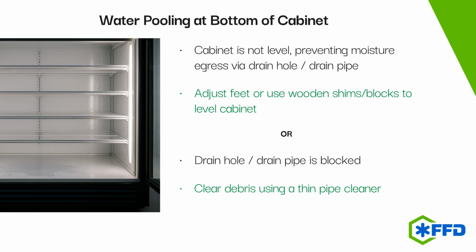It can also be caused when the drain hole or drain pipe becomes blocked. This is usually located inside, at the center bottom of the cabinet. Use a thin pipe cleaner to clear any debris and allow moisture to egress freely.